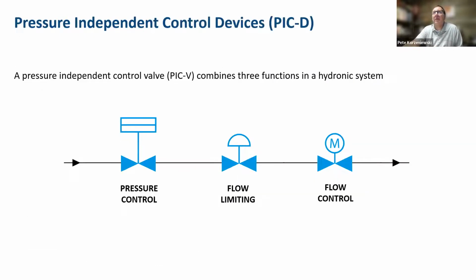So really briefly on pressure independent control valves and devices, the pressure independent control valve came onto the market. It essentially became a 3-function valve, and we'll start here on the right hand side, it allows us to do our flow control. So it's got a modulating flow control valve as a component of it. It also takes care of that pressure control. It's got the ability to sense that incoming pressure, sense changes, and eliminate that. And then lastly, it's a flow limiting device. The last thing we want to do as we're trying to control flow into our terminal units or air handling units is to overflow that unit.